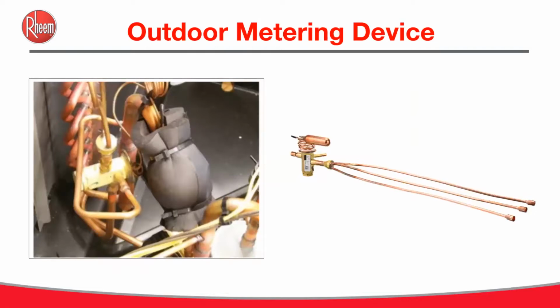Outdoor metering device. Again, another component that's not required on an AC is a metering device in the outdoor unit. As the picture shows here, this is a TXV. On some of your communicating systems, you may have an EEV or an EXV, which is an electronic expansion valve. The thermal expansion valve is designed to maintain approximately 10 to 15 degrees superheat, whereas with inverter products and the use of an EEV, we can have superheat as low as 6 degrees Fahrenheit.